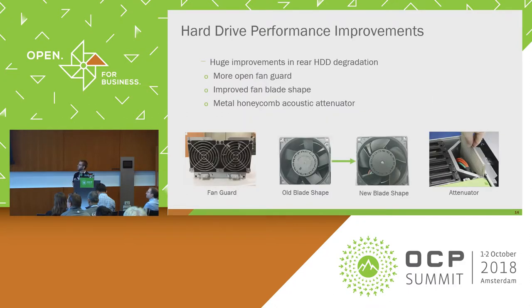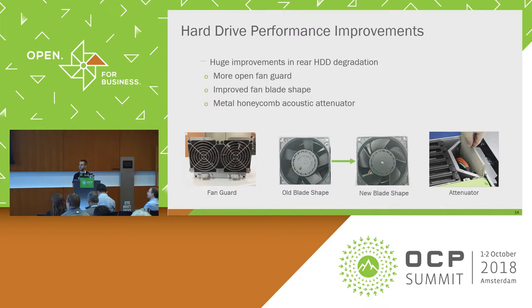To achieve those improvements, we made several mechanical and thermal design changes. We changed the fan guard on fans near the back row of drives — before it was stamped sheet metal with sharp flat corners that increased acoustic vibrations as air pulled through. We moved to a wire-shaped traditional fan guard, which reduced noise, combined with modifying the physical shape of the fan blades to also reduce acoustic noise. We also added an acoustic attenuator at the back of the chassis — a honeycomb mesh that attenuates acoustic noise coupling from the fans to the hard drives. These combined improvements significantly reduced hard drive degradation, especially under high PWM.